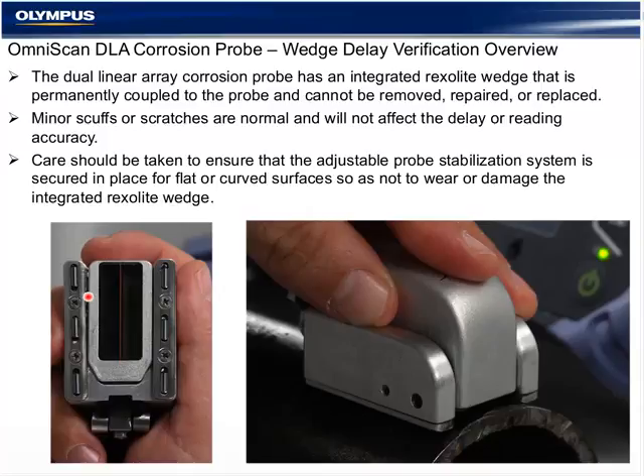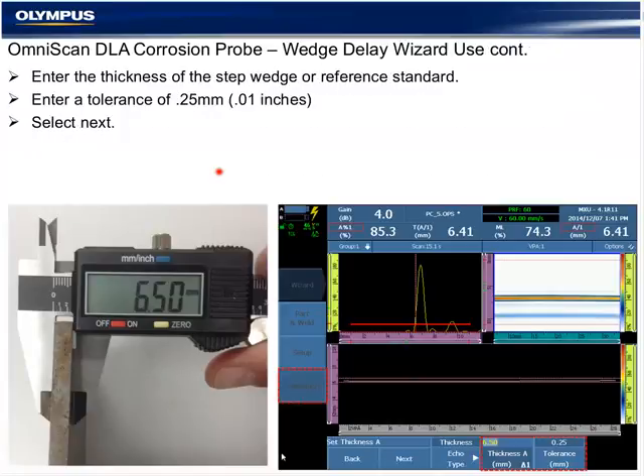Care should be taken so that the guides are adjusted properly, either for flat or for piping, so that we don't wear the Rexolite wedge or damage it unnecessarily. There's a very easy adjustment here. This is also made more clear in the full sections and the promotional video. The device loosens, allows the probe to be coupled to a pipe diameter and placed to provide support and stability for good readings. The wedge delay function is directly related to the accuracy of the thickness readings, which is what this inspection is all about.